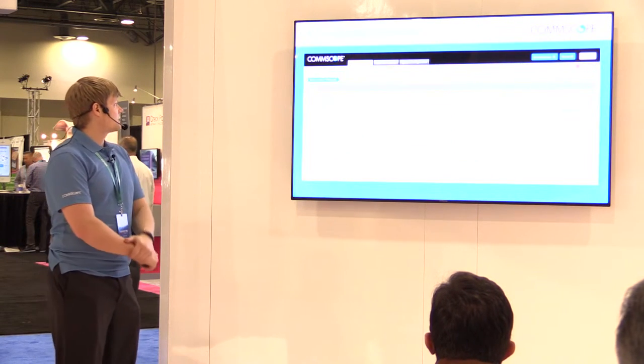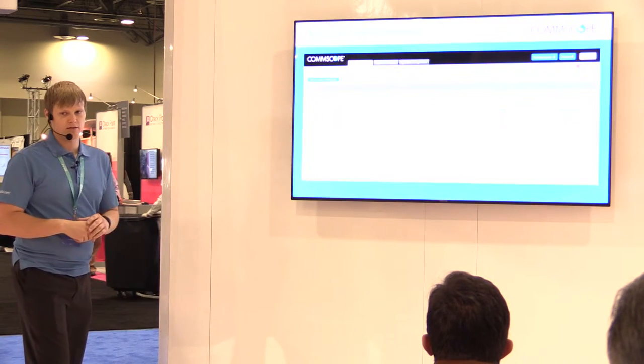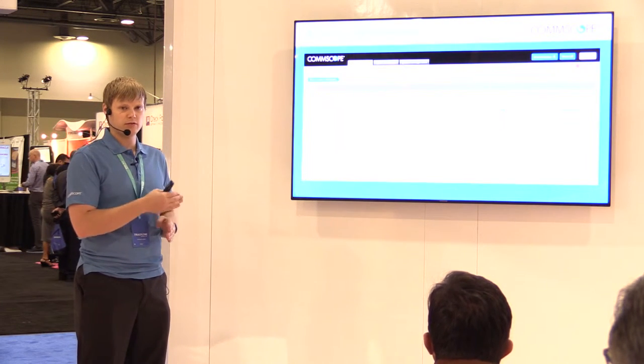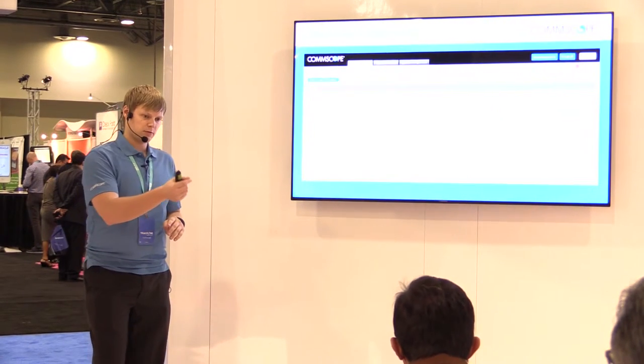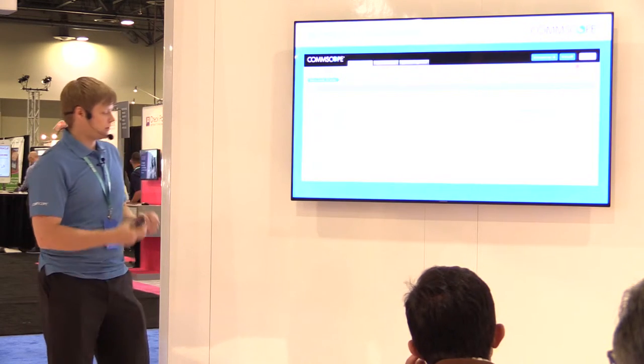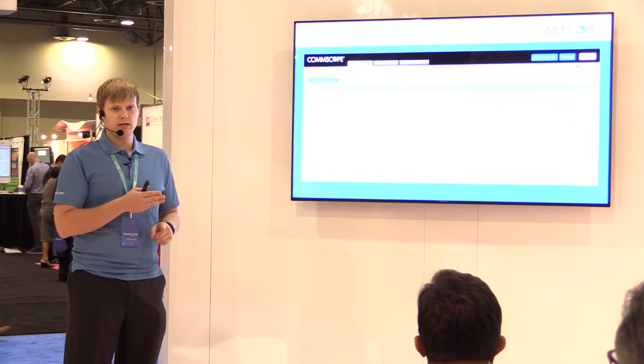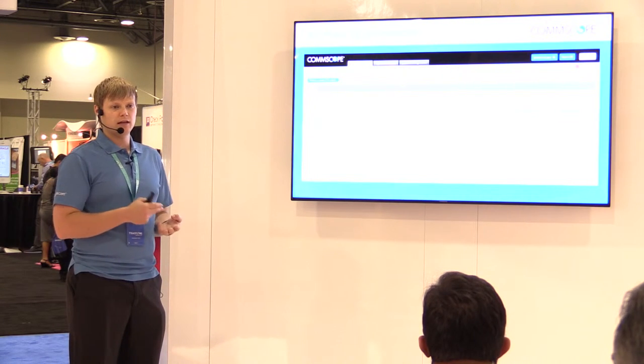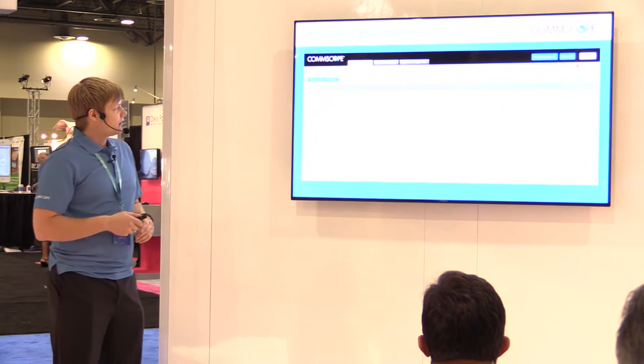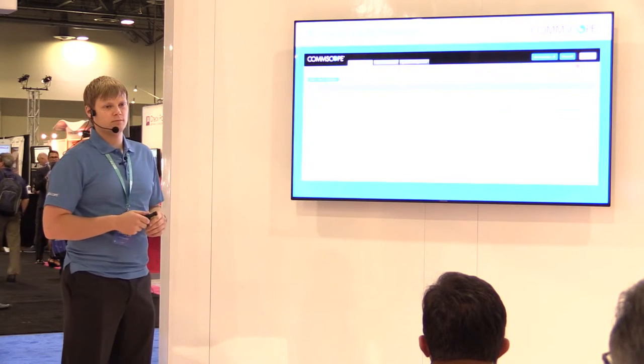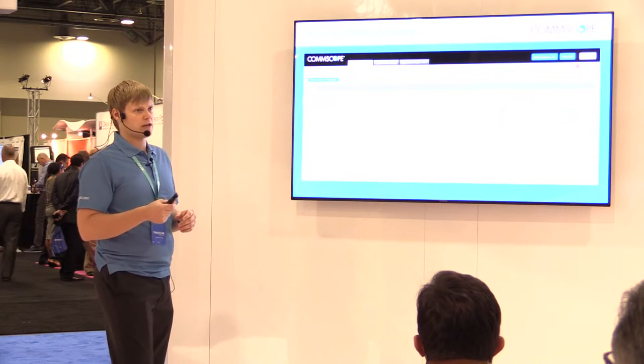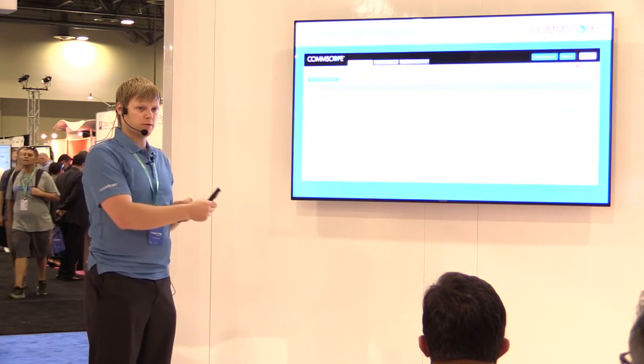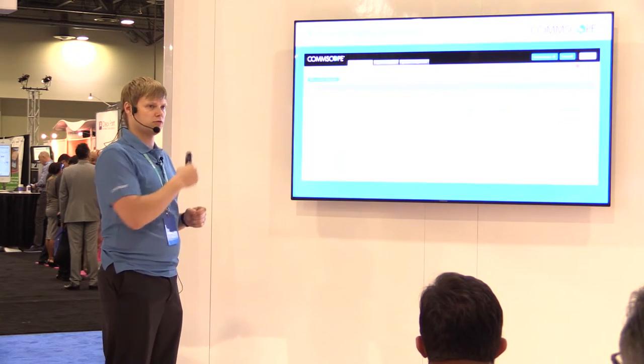This is probably the best and most powerful feature of the ION-E — automatic signal detection. Automatic signal detection allows you to get every piece of information about the RF signals you've inputted that you need to commission the system. You plug your base station into the RFD card — your RF donor card — and you're going to get the carrier, the center frequency, the band, the bandwidth of the signal, as well as the cell ID. It provides you all the information needed to decode. Another great feature is that in the web GUI everything is searchable. So whenever you're creating your signal sets — say, I want this sector on this UAP — you can search by the cell ID. If you know that a particular zone needs this cell ID, you can search for it, drag, drop, and then you're done.